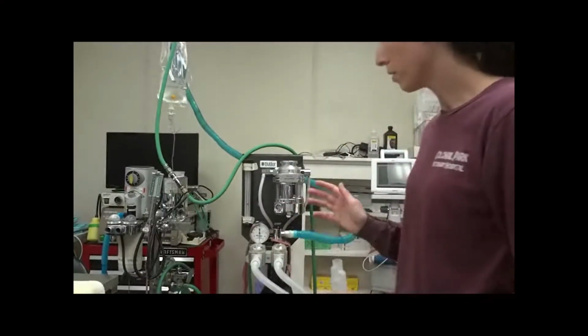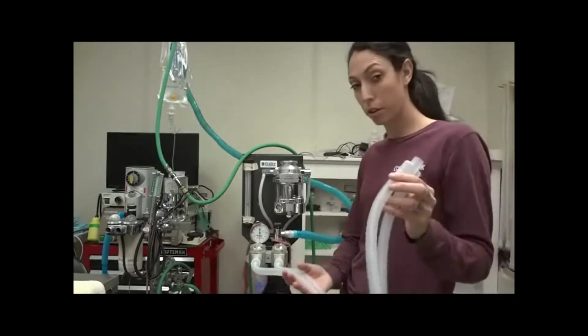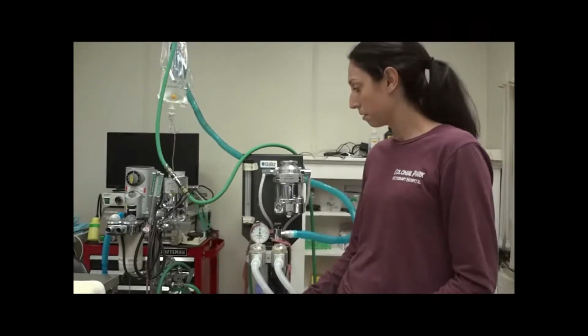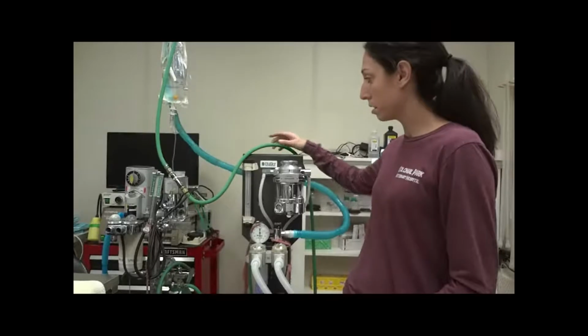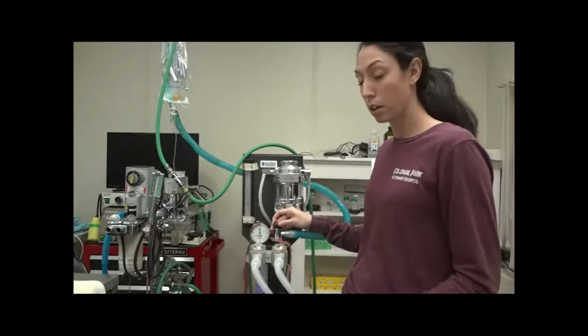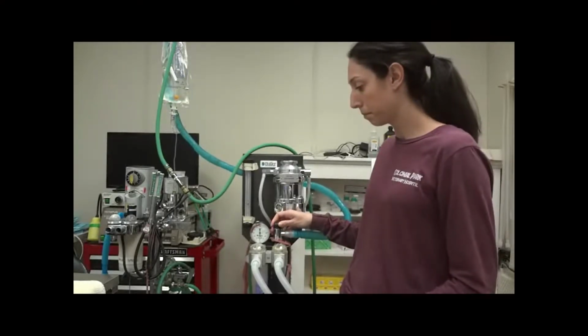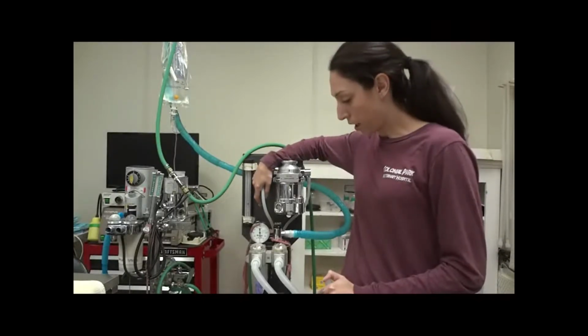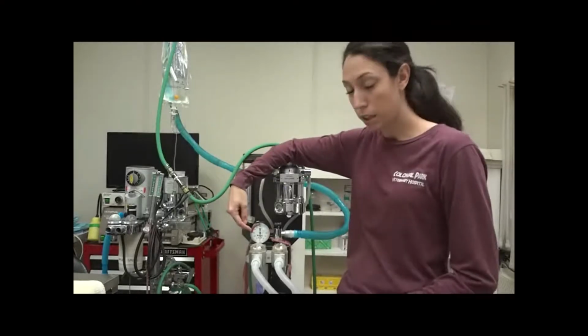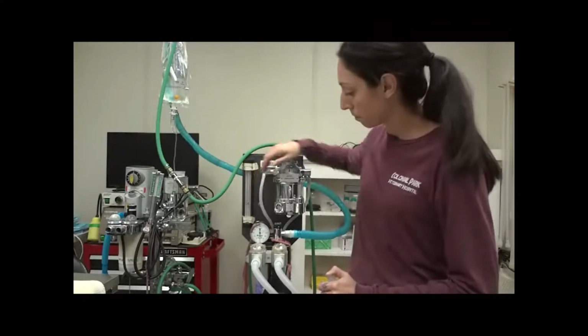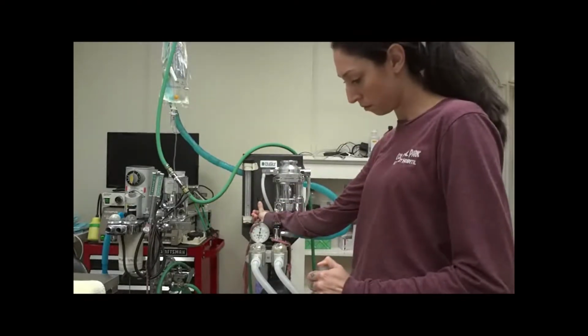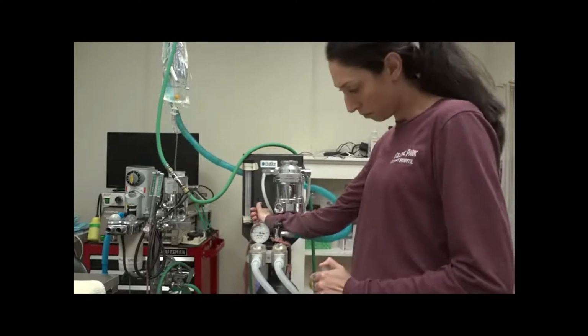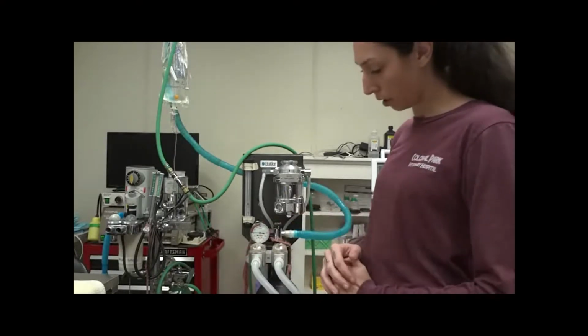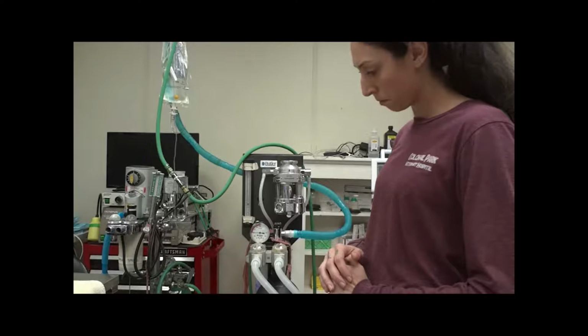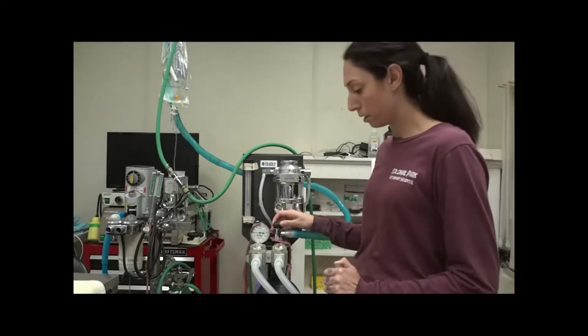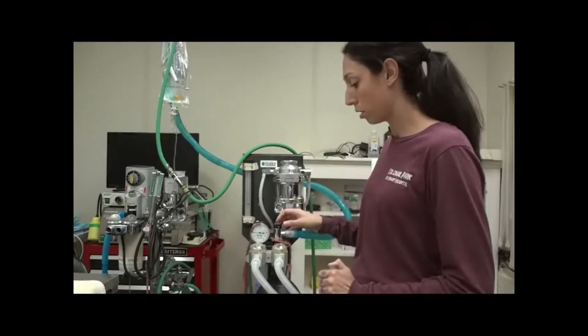We're going to be performing a leak test on our anesthesia machine. So we've got our rebreather on, our reservoir bag, and our oxygen line set up. Alright, so we're going to close our valve completely. We're going to push our flush valve until the reservoir bag fills up completely, and it should stay at the 30 mark. If it does not, then we have a leak. So as you can see, it's staying there. Alright, now we're going to open our relief valve, and all the oxygen should leave.